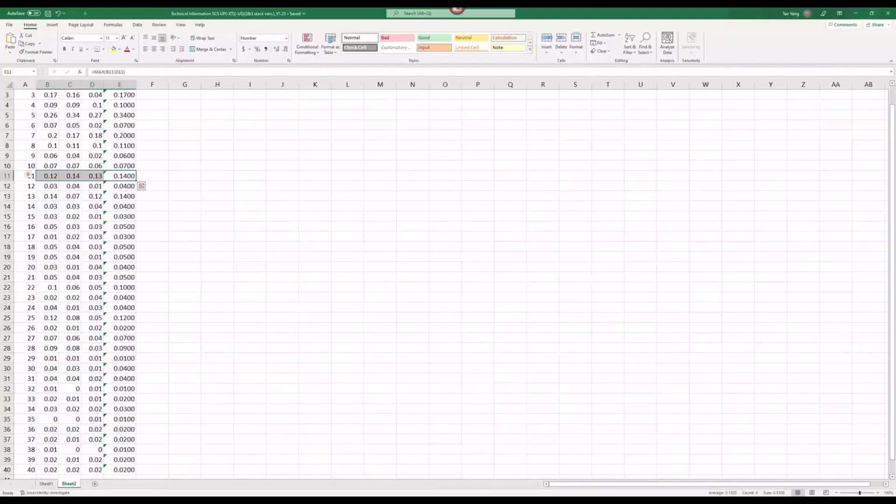As you can see, the violation is valid actually, because at my 11th order, I have about 0.14, and at the 13th order, I have 0.14 as well, percent of the current injection, which is huge, to be honest with you.